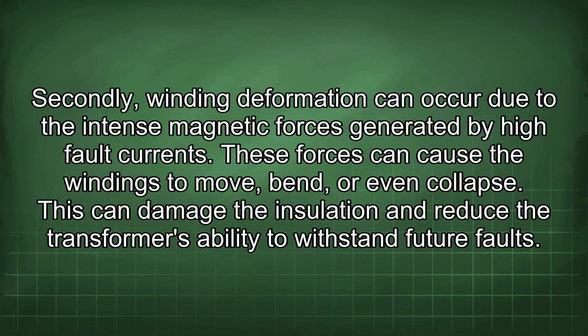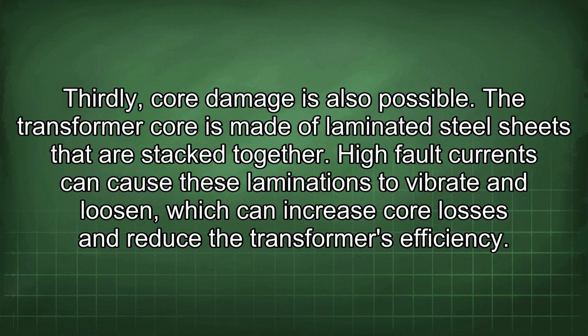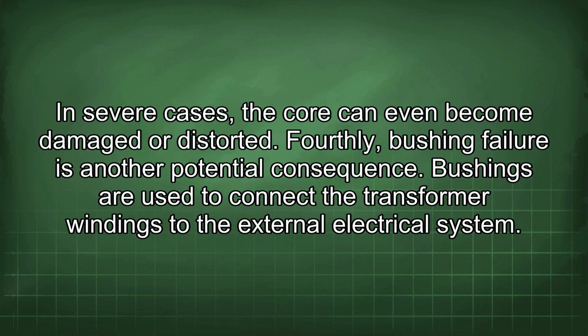Secondly, winding deformation can occur due to the intense magnetic forces generated by high fault currents. These forces can cause the windings to move, bend, or even collapse. This can damage the insulation and reduce the transformer's ability to withstand future faults. Thirdly, core damage is also possible. The transformer core is made of laminated steel sheets that are stacked together. High fault currents can cause these laminations to vibrate and loosen, which can increase core losses and reduce the transformer's efficiency. In severe cases, the core can even become damaged or distorted.